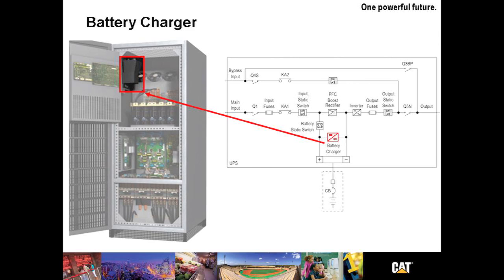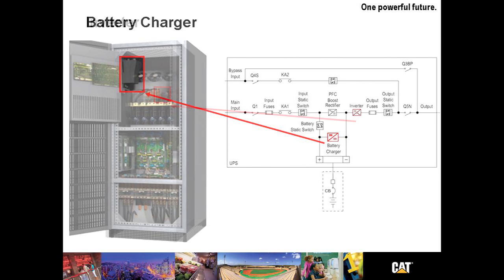The charging system incorporates independent regulation and monitoring devices. Voltage regulation by battery voltage measurement circuits. Charge current regulation by battery voltage measurement circuits. Battery voltage monitoring circuits, which is independent from the regulation system. And a charge current monitoring circuit, also independent from the regulation system. DC ripple is less than 1% of the DC voltage. There is a battery meter that indicates the remaining backup time. This can be accessed from the front screen, which we'll look at in a few moments.